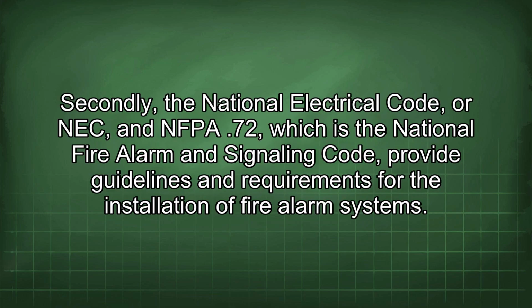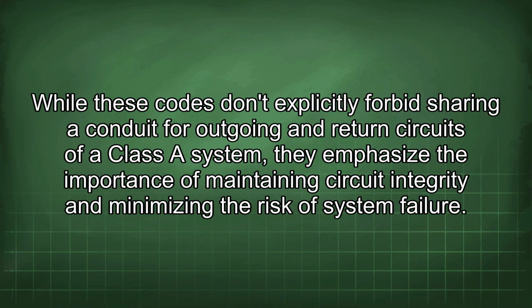Secondly, the National Electrical Code, or NEC, and NFPA 72, which is the National Fire Alarm and Signaling Code, provide guidelines and requirements for the installation of fire alarm systems. While these codes don't explicitly forbid sharing a conduit for outgoing and return circuits of a Class A system, they emphasize the importance of maintaining circuit integrity and minimizing the risk of system failure.